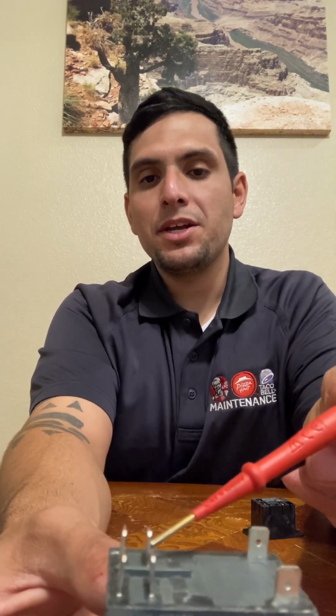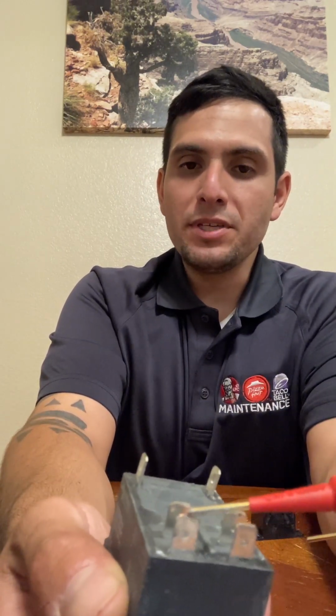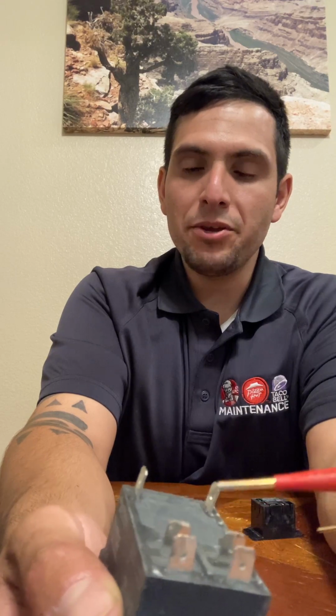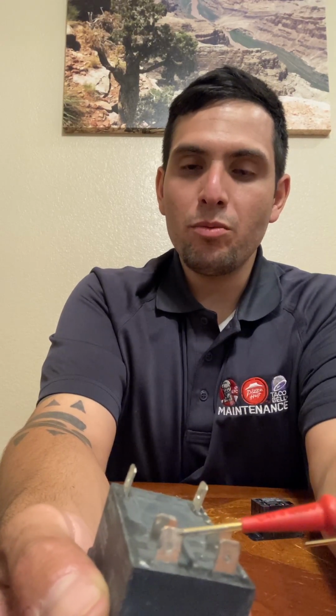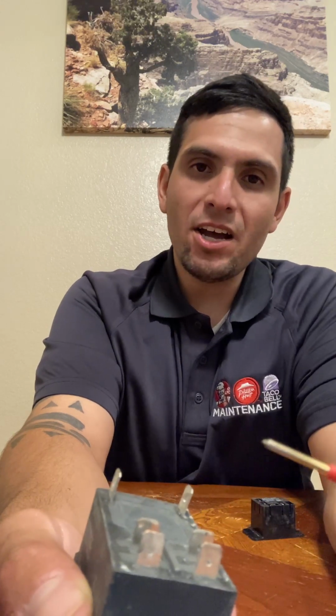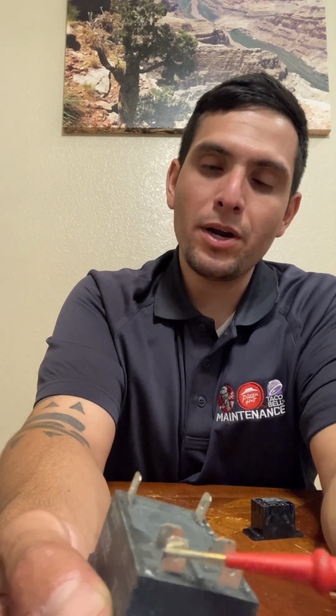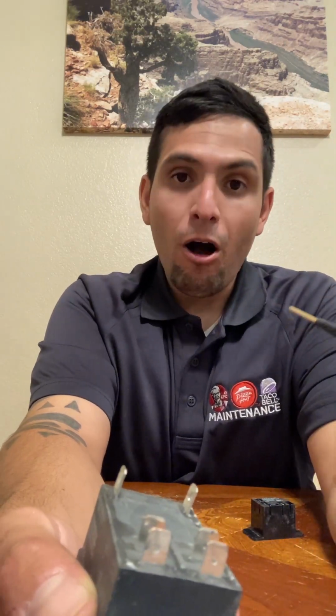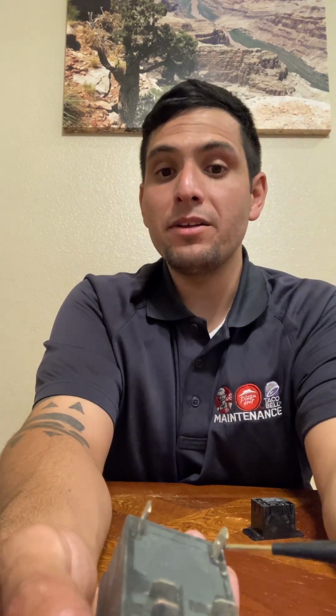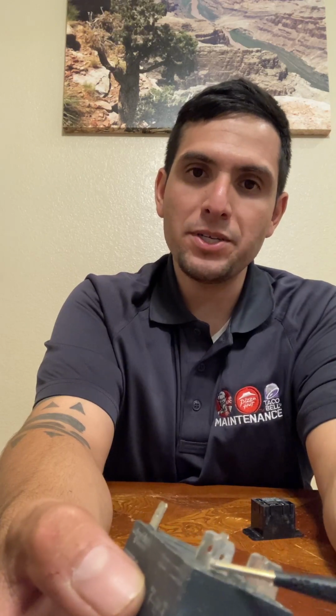But basically, if you see two relays where this terminal is hot and this terminal is hot, but then you get to one relay and this one's not hot, you know that relay is not opening like it should be, or closing depending on how you word it, but it's not sending power to the element like it should be. And you know that relay is bad if it's not sending power when it's calling for heat. As long as it's getting the right supply voltage, or if it's getting the right control voltage, then it should be sending power to the heating element.